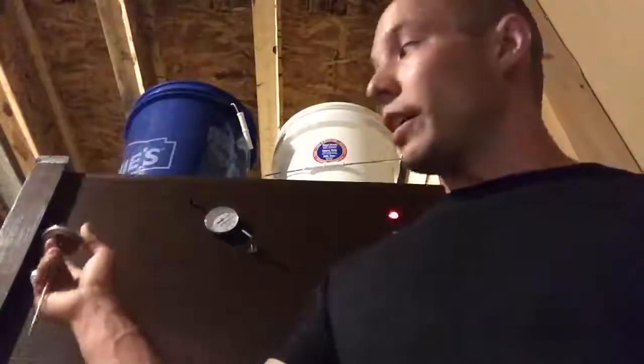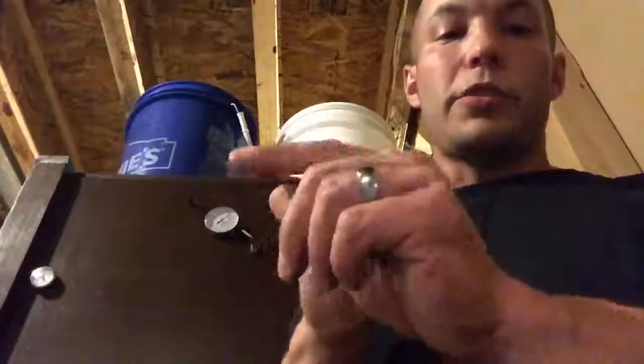You're going to want to calibrate both of those. This one will end up going into your incubator just like this — the probe goes in and determines the temperature. That's your dry bulb.